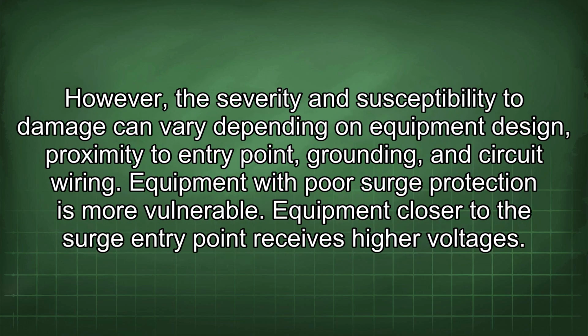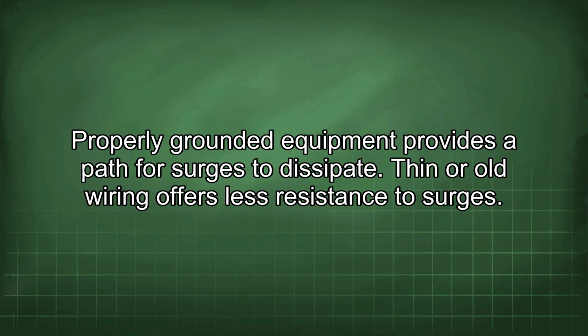However, the severity and susceptibility to damage can vary depending on equipment design, proximity to entry point, grounding, and circuit wiring. Equipment with poor surge protection is more vulnerable. Equipment closer to the surge entry point receives higher voltages. Properly grounded equipment provides a path for surges to dissipate. Thin or old wiring offers less resistance to surges.